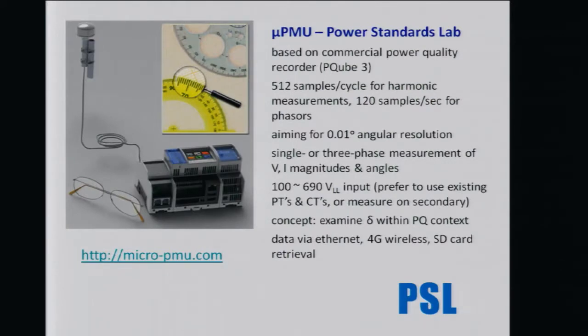Power Standards Lab is building on their already commercial P-Cube power quality instrument, adding a high-precision GPS receiver to be able to make that time stamping and measure the voltage phase angles, in addition to the voltage magnitudes and the currents. The target resolution is 10 millidegrees, which is very precise. Typically at the transmission level, about a degree or so of accuracy is okay for the kinds of power flows you're interested in and the kinds of phase shifts, which can be in the tens of degrees between locations.